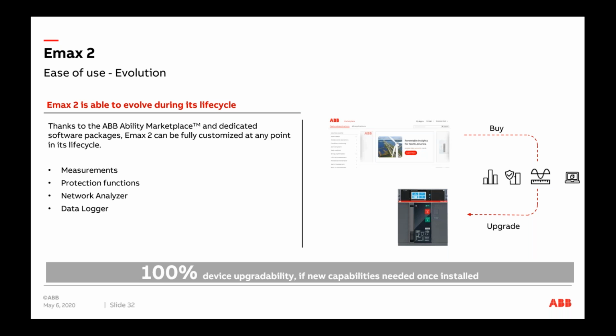Although you don't receive a physical product, what you receive is a certain code which allows us to upgrade the breaker. So with that, a certain breaker at a certain point of the life cycle of the system requiring certain functionality, when we see evolution of requirement of functionality, this is where Emax 2 is future-proof. So a simple Emax 2 with a Ekip Touch trip unit can be upgraded with any functionality that we look at. Now, that's what I have, and I'll be happy to answer any questions as we go along.